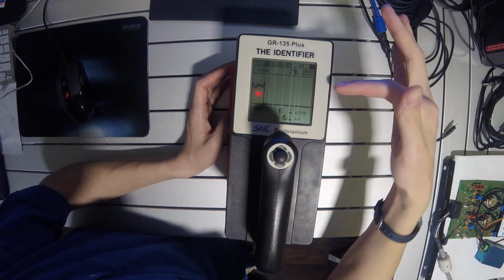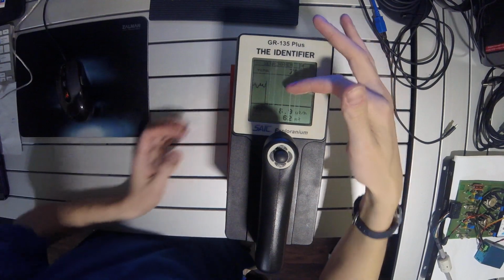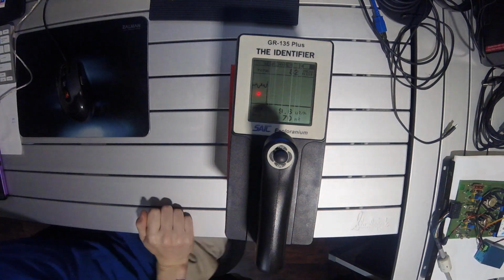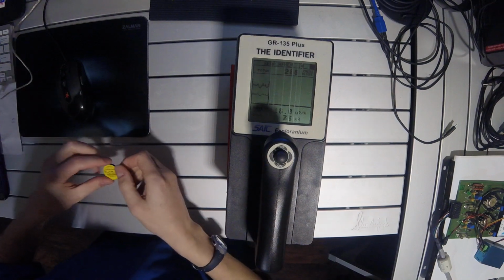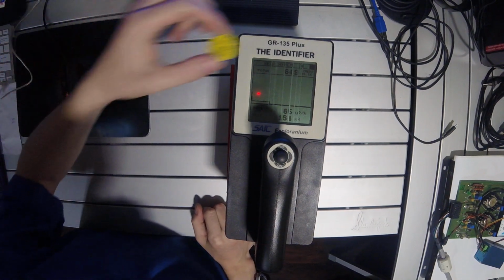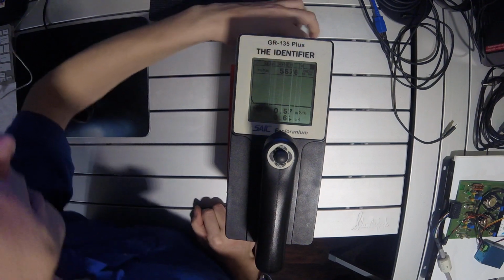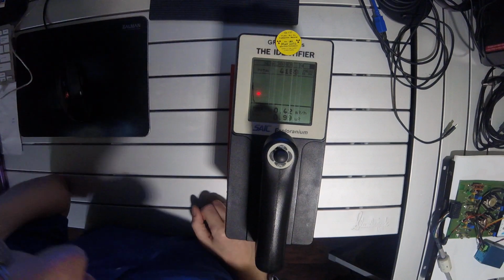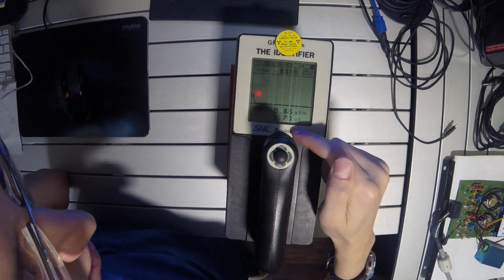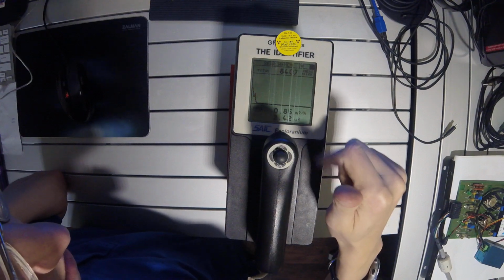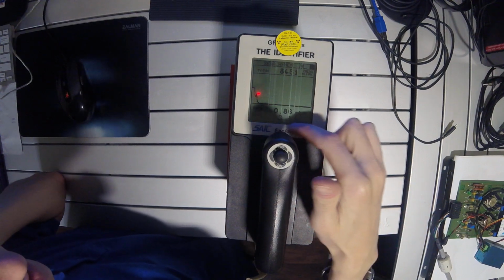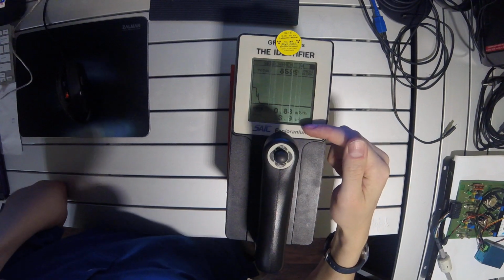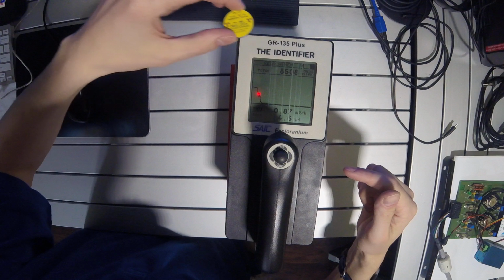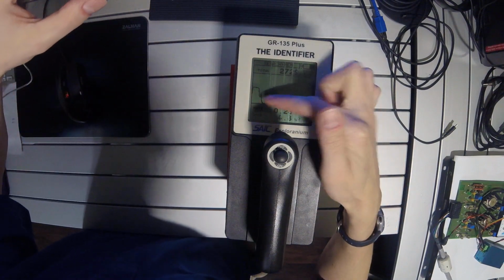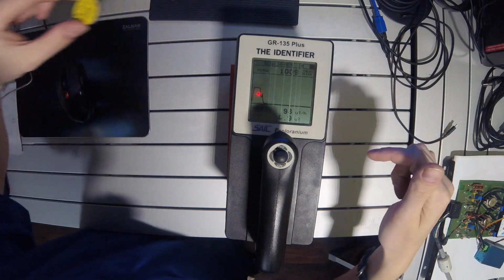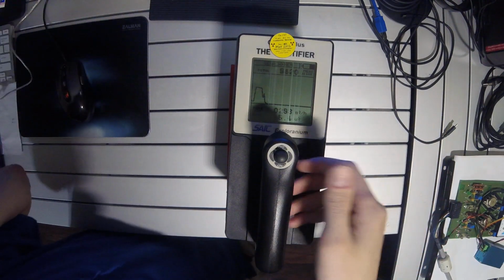There's a continuous plot of dose rate. So first we'll test this out with a cesium-137 check source. This is 10 microcurie. So if you put it down on the screen, see the dose rate going up to around 0.86 milliroentgen per hour, and then the total accumulated dose is increasing more rapidly. You can see as you move this further away, the graph responds proportionally.